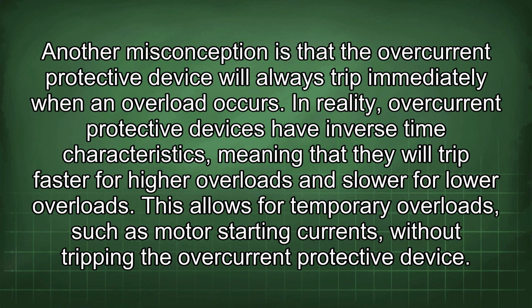In reality, overcurrent protective devices have inverse time characteristics, meaning that they will trip faster for higher overloads and slower for lower overloads. This allows for temporary overloads, such as motor starting currents, without tripping the overcurrent protective device.